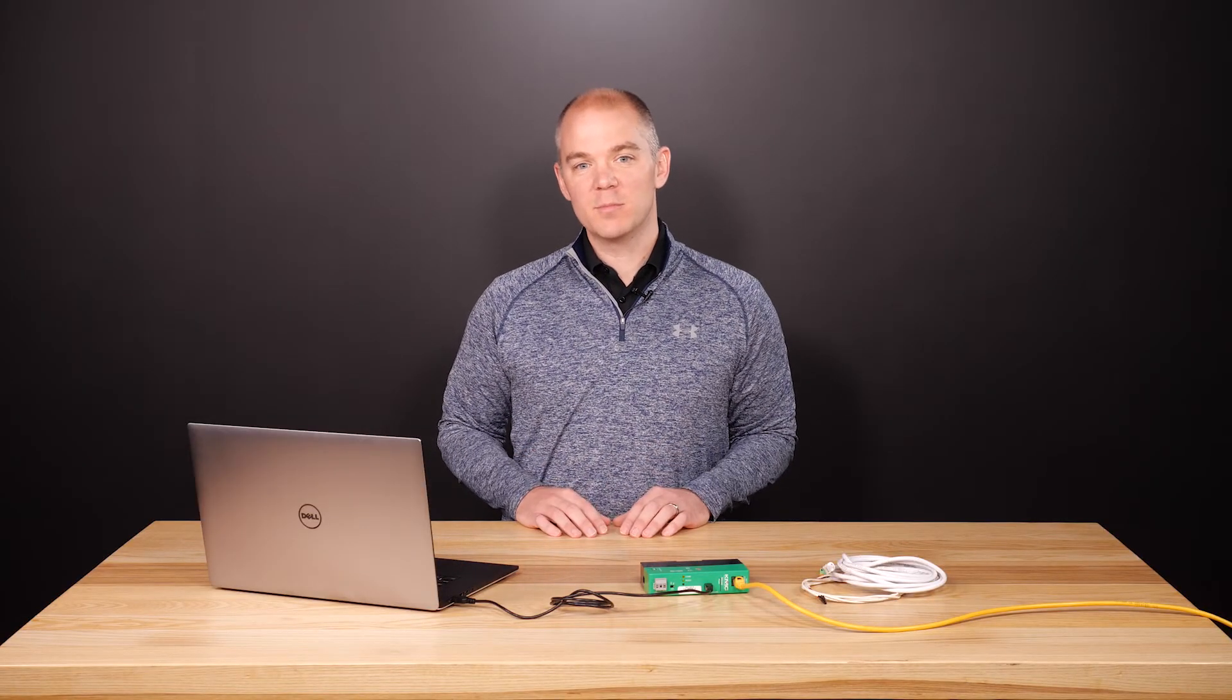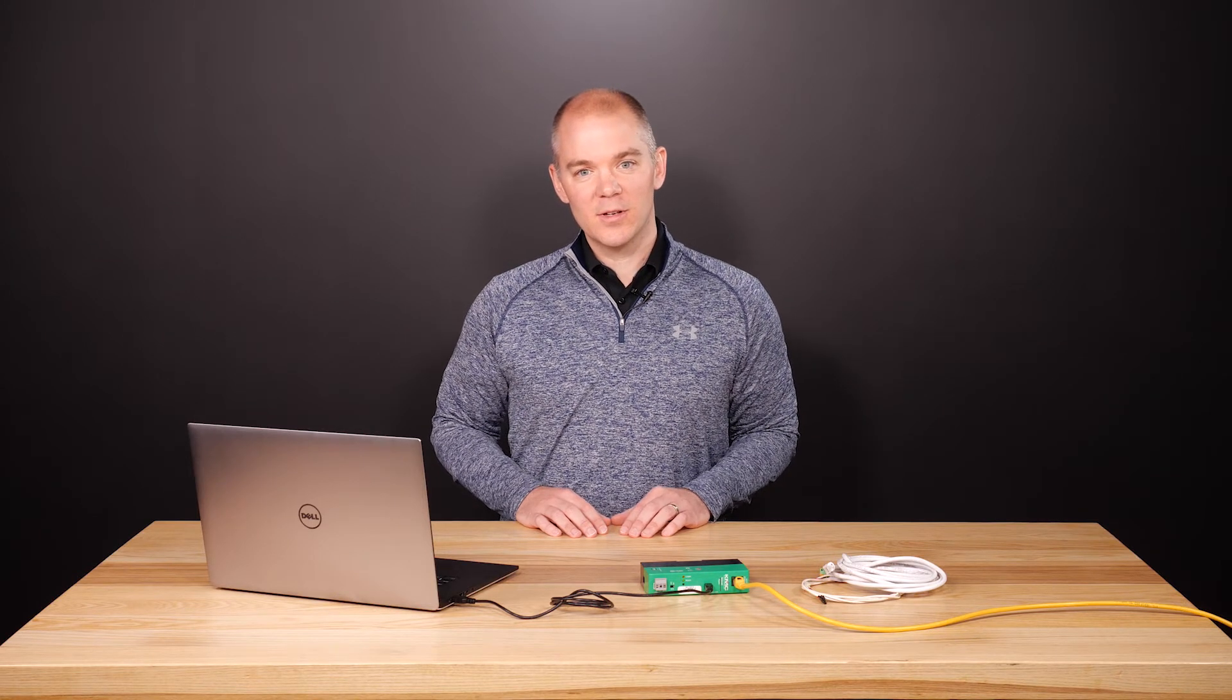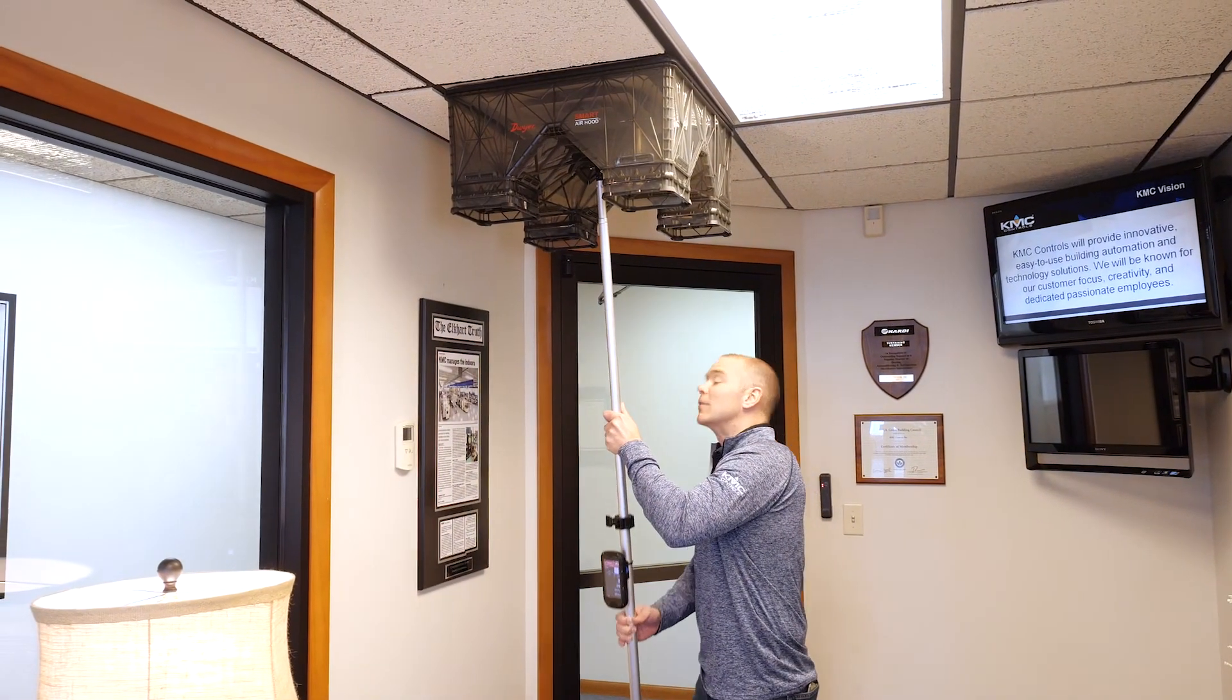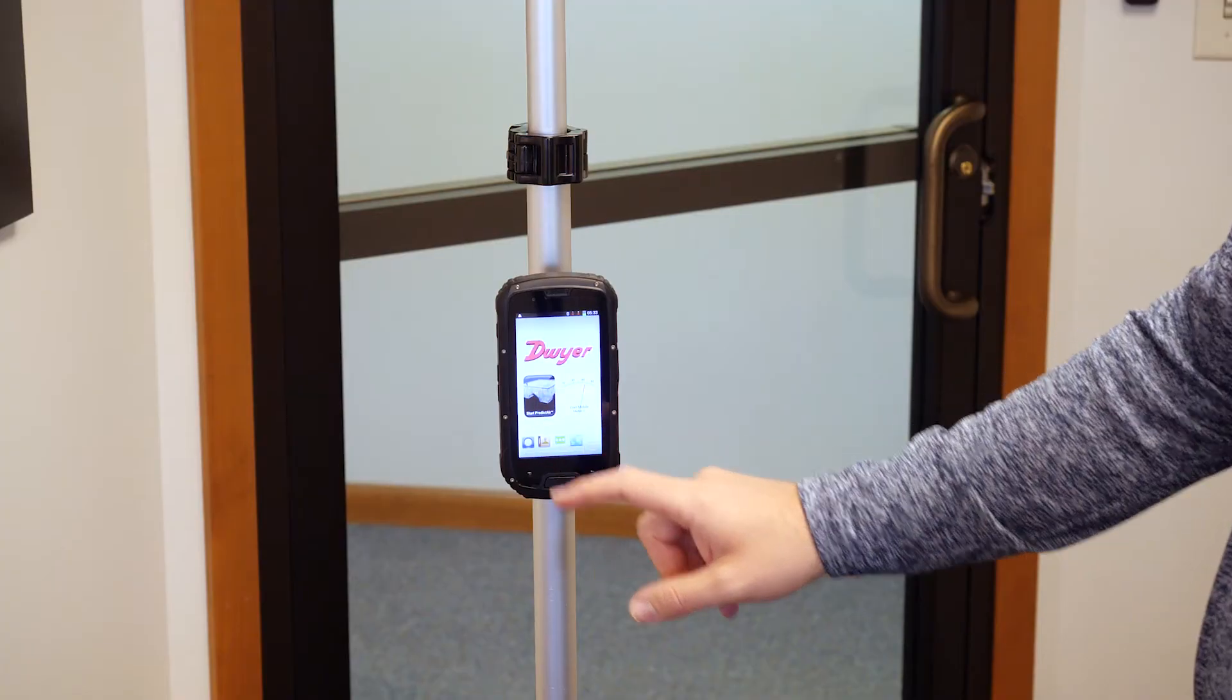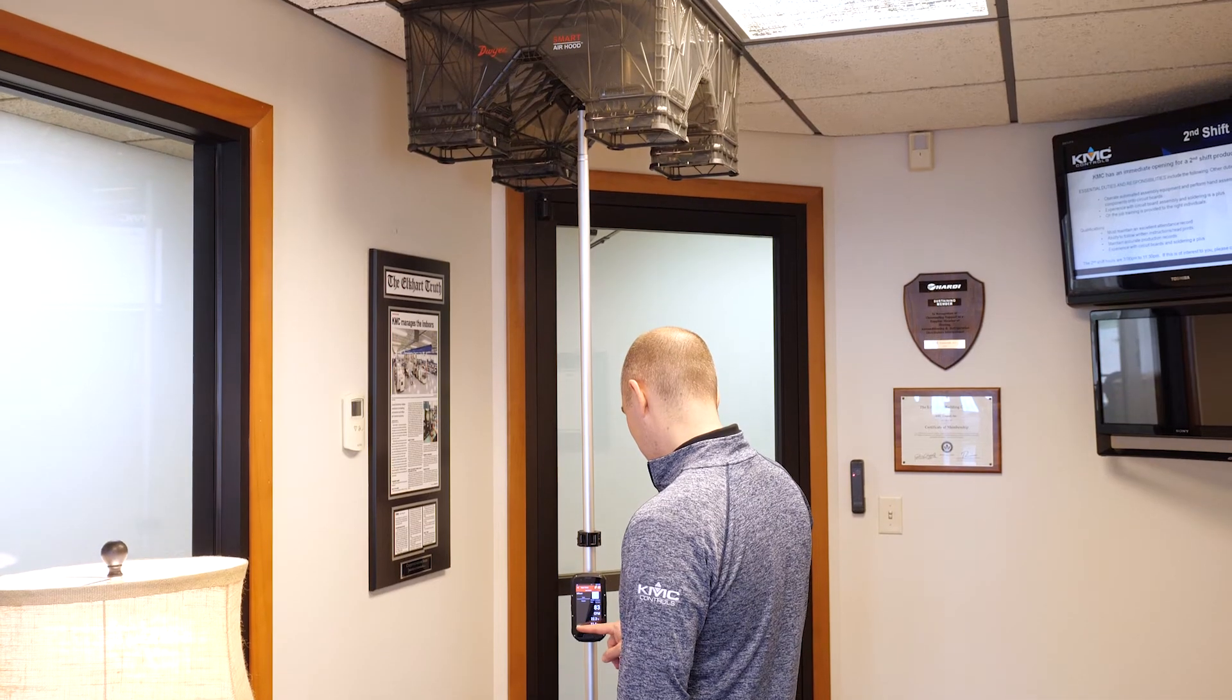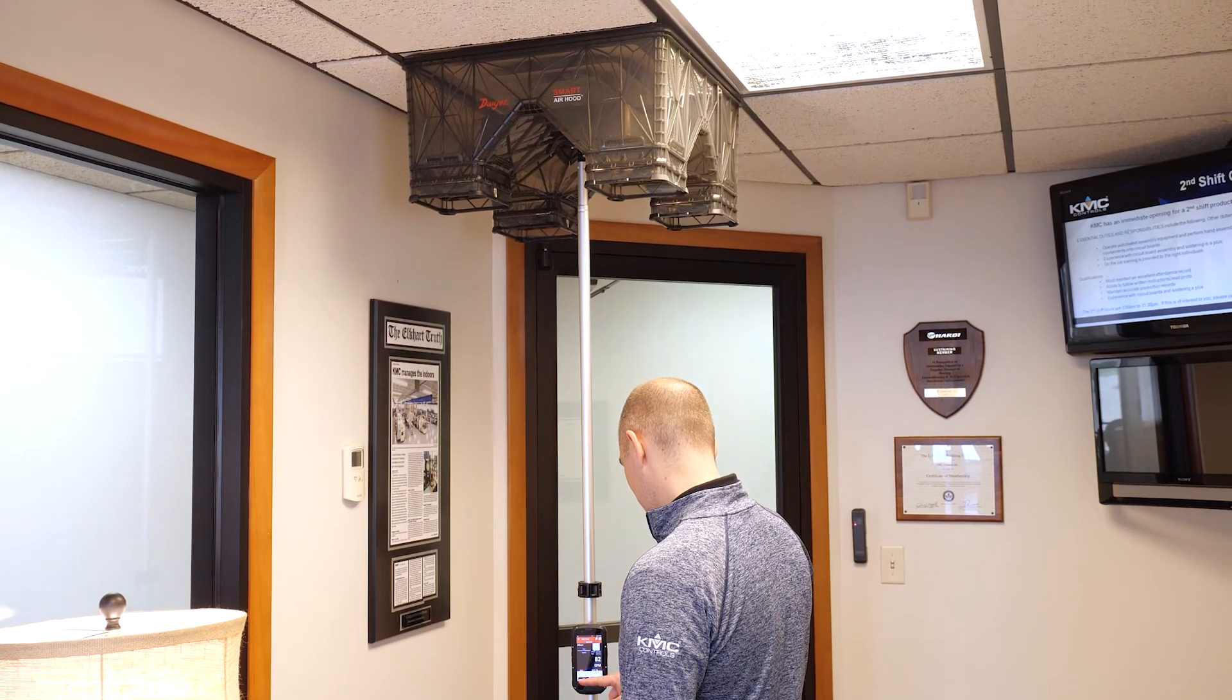The readings displayed on the VAV balancing page are the actual uncorrected airflow readings as measured by the controller. The controller will direct the VAV to open the damper to the highest maximum airflow set point. It will take a moment for the actual airflow value to stabilize at its maximum. With the flow hood, measure and note the actual airflow. Enter this value into the measured max box.